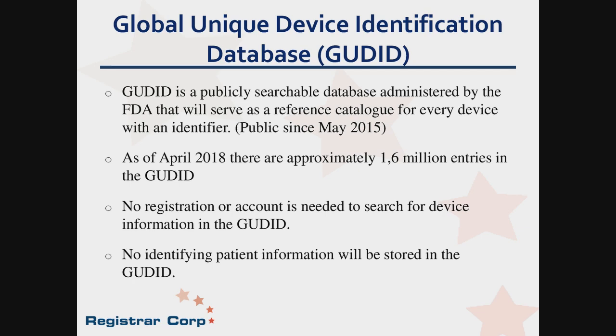FDA requires that you submit the UDI into a database, which is called the Global Unique Device Identification Database. This is a public database. It's public since May 2015. Around April, FDA told us they have approximately 1.6 million entries in that database, and it's constantly rising. There is no registration necessary. It's a public database. You can go in and you can search for a company name, for products. If you have the UDI number, you can also put in the UDI number, and you can get a lot of information about that device. No patient data are in that database.